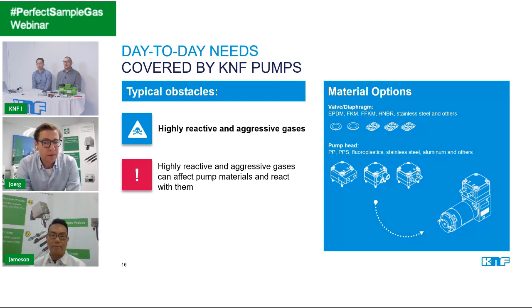Contamination means more like the contamination of the environment. For example, if you don't choose the right sealing technology or sealing materials in the pump, the pump loses its tightness, especially in the ATEX area - it's not really good if the gas comes out of the pump. Also, highly reactive gases have influence on the pump material. If you don't choose the right head material, you might get problems. So this is what is meant by it.